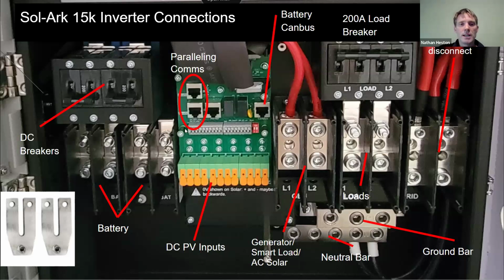The accessories connections here I'm going to go over on a later slide, but these are your solar inputs: 3 independent solar inputs, positive, negative for 1, positive, negative for 2, positive, negative for 3. You have 4 inputs per MPPT just so you can parallel at the inverter. So 3 independent controls here for that. The generator, CTs, rapid shutdown, that'll all occur here on the accessories bar in the center.